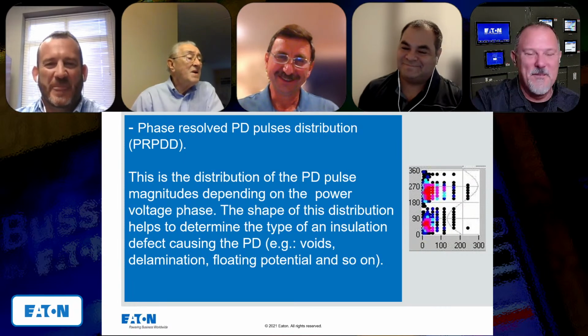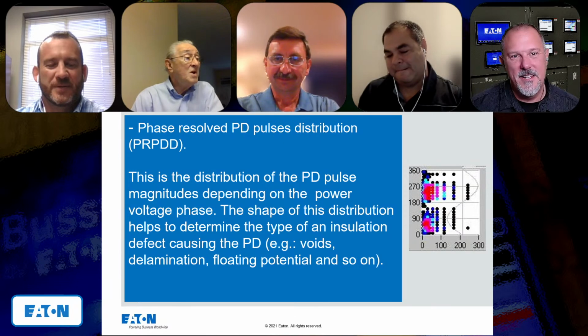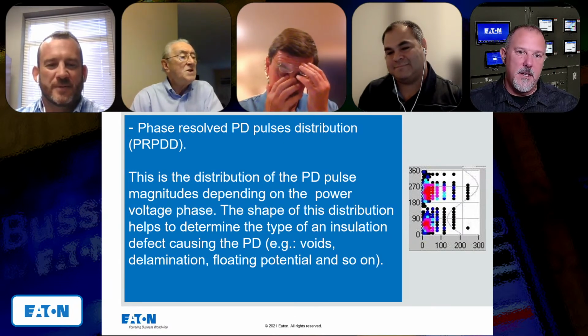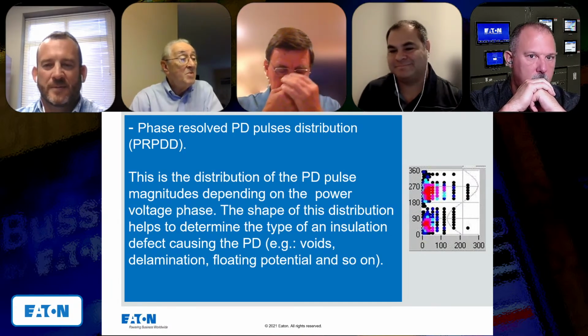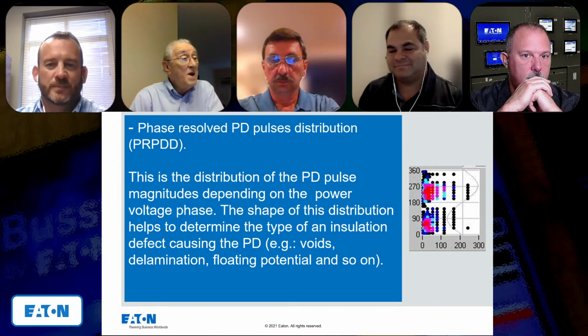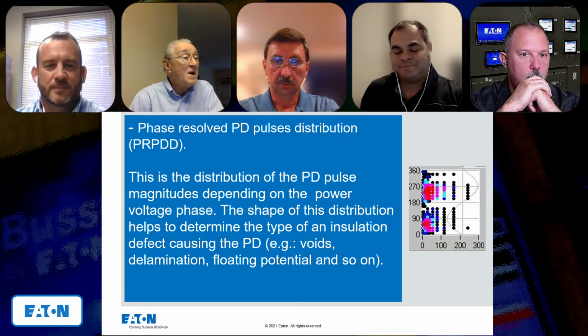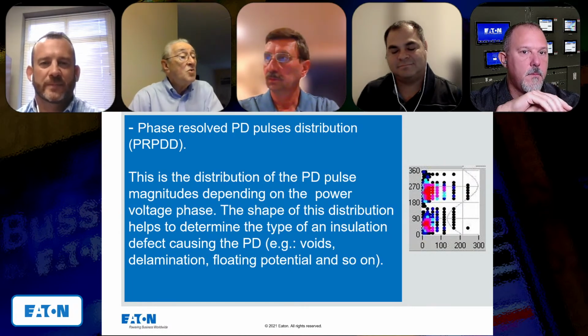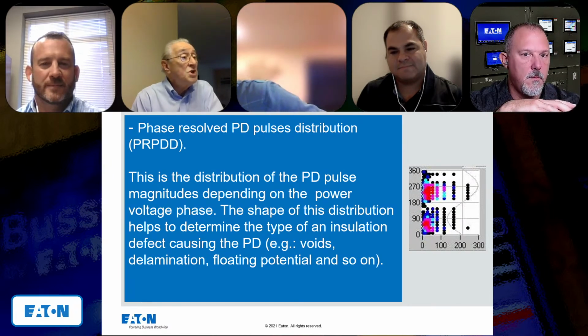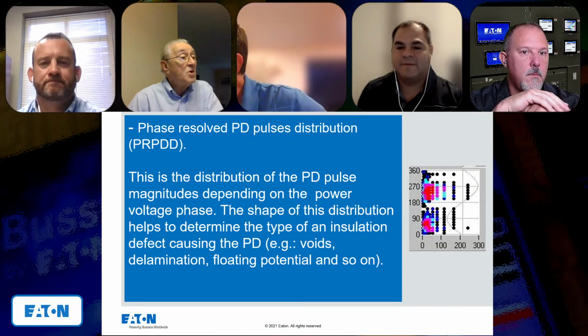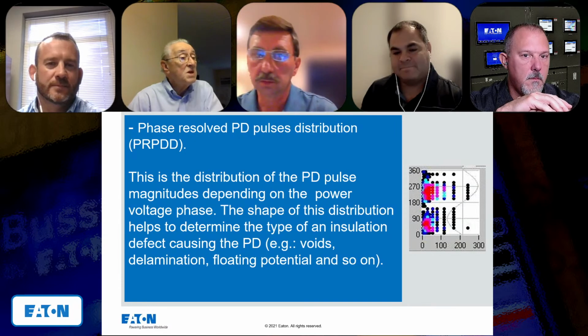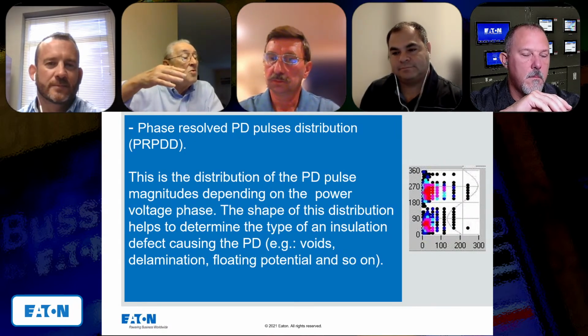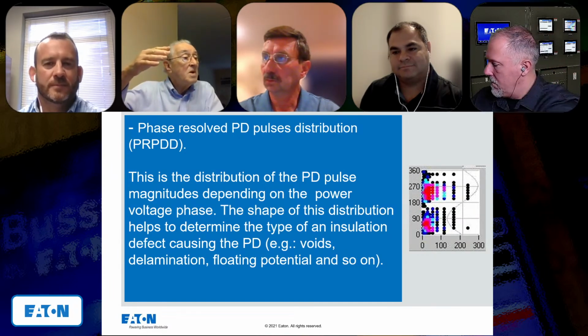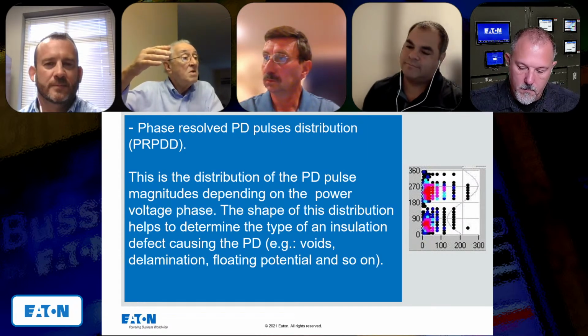I'd like to add that this characteristic, phase-resolved distribution, is very useful. But again, I'd like to go back to the integrated parameter. These parameters, partial discharge intensity or Qmax, are also very important, and sometimes it's enough to see this parameter to conclude that it's necessary to check the condition of the insulation. For example, if the customer sees that the integrated power or Qmax increased, they can check the equipment.